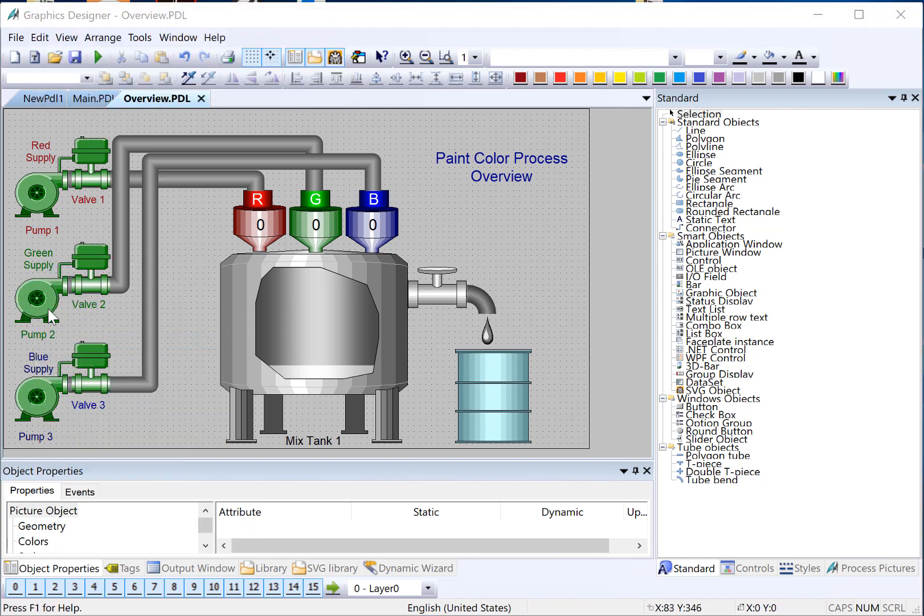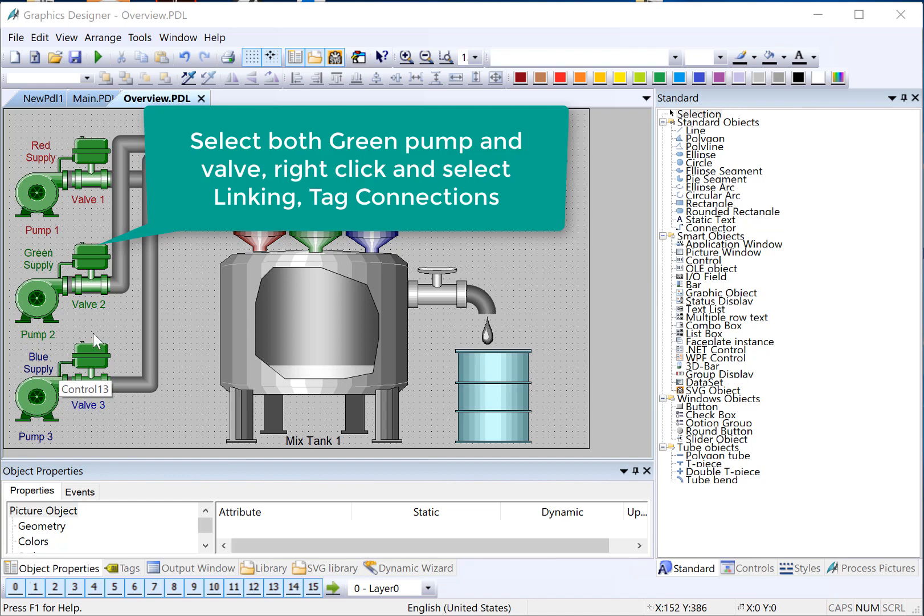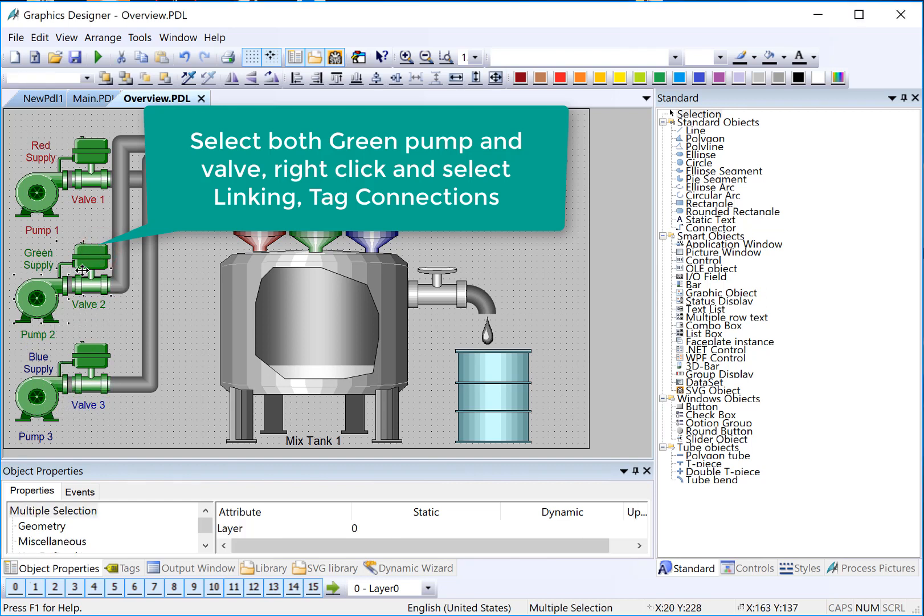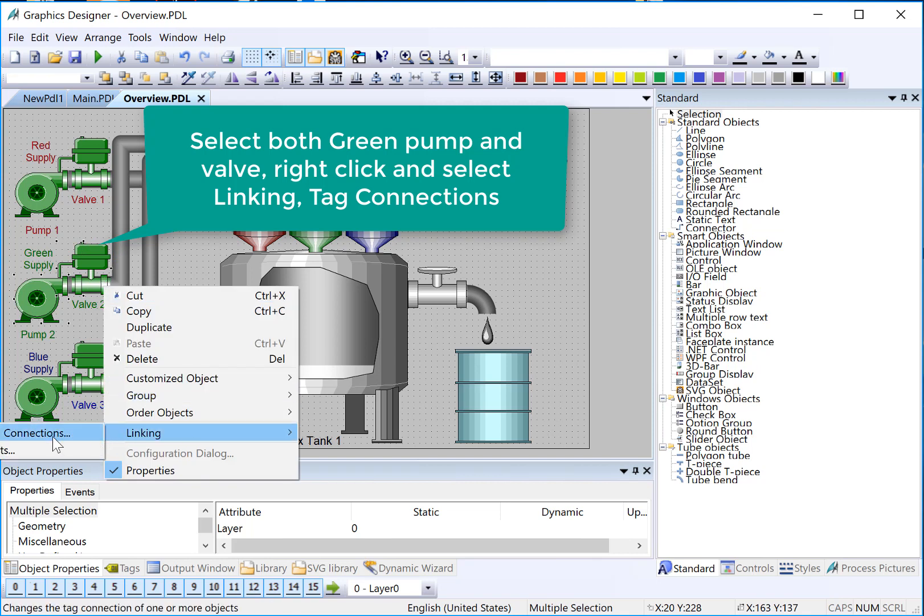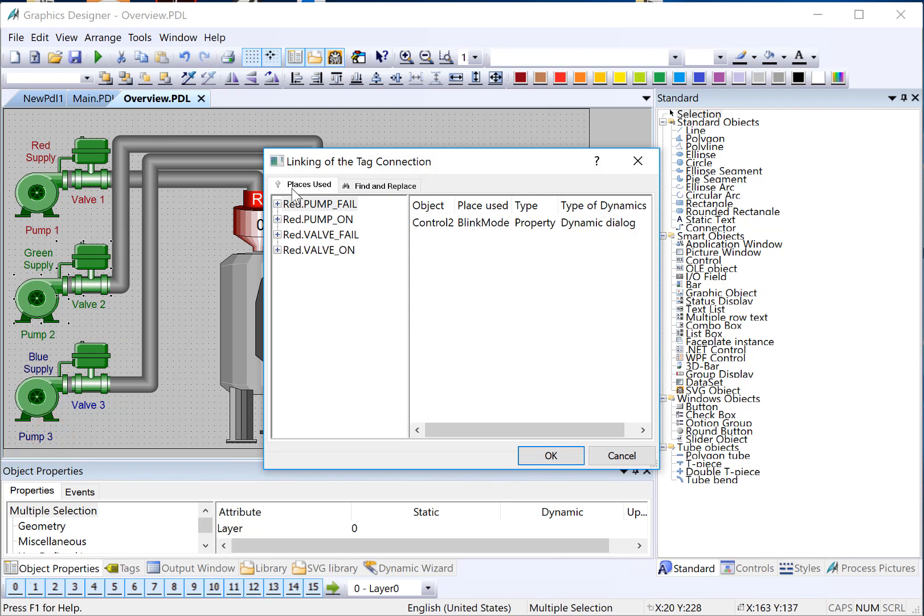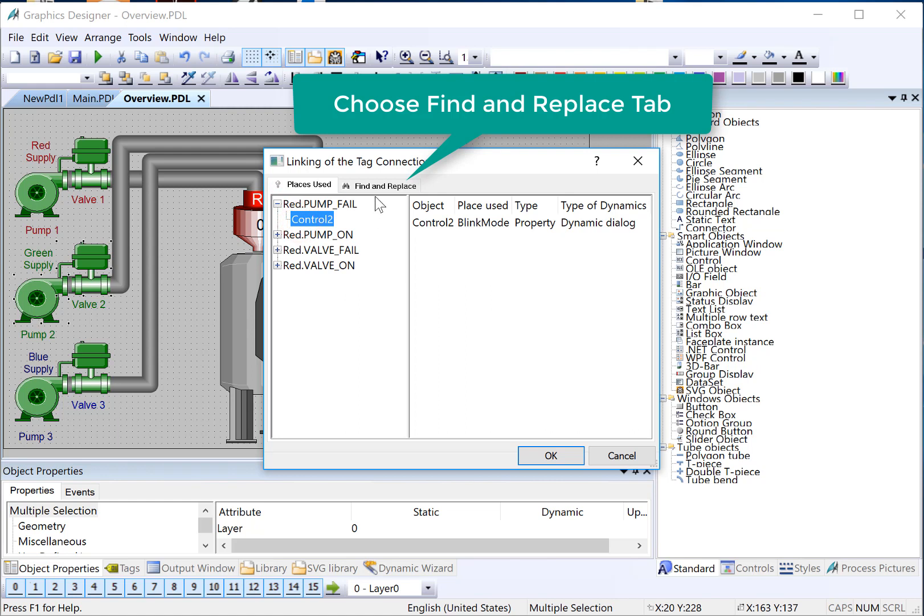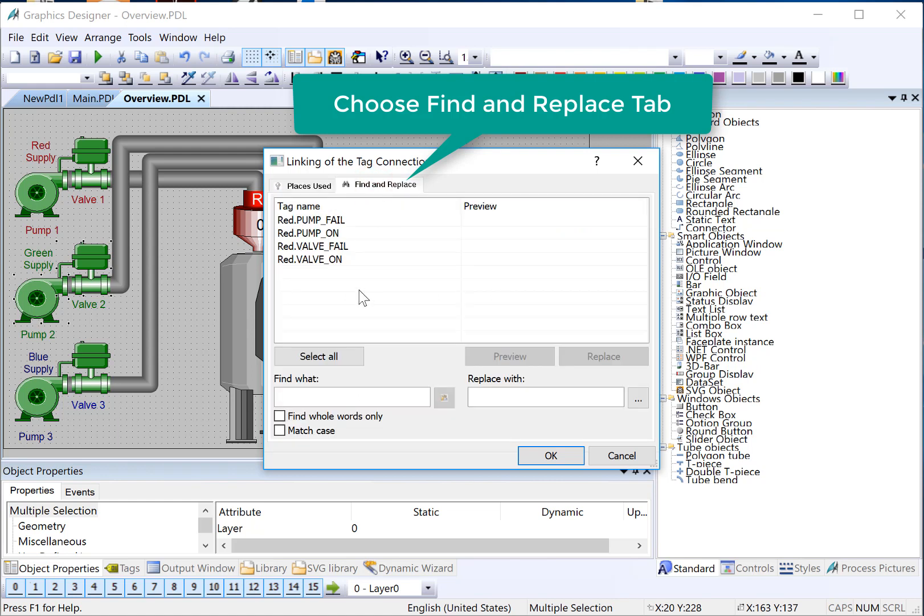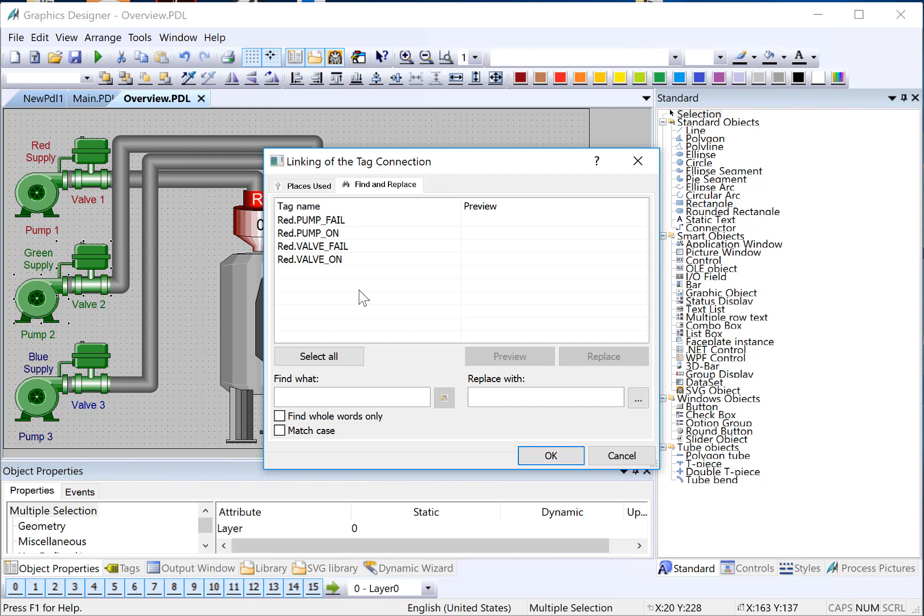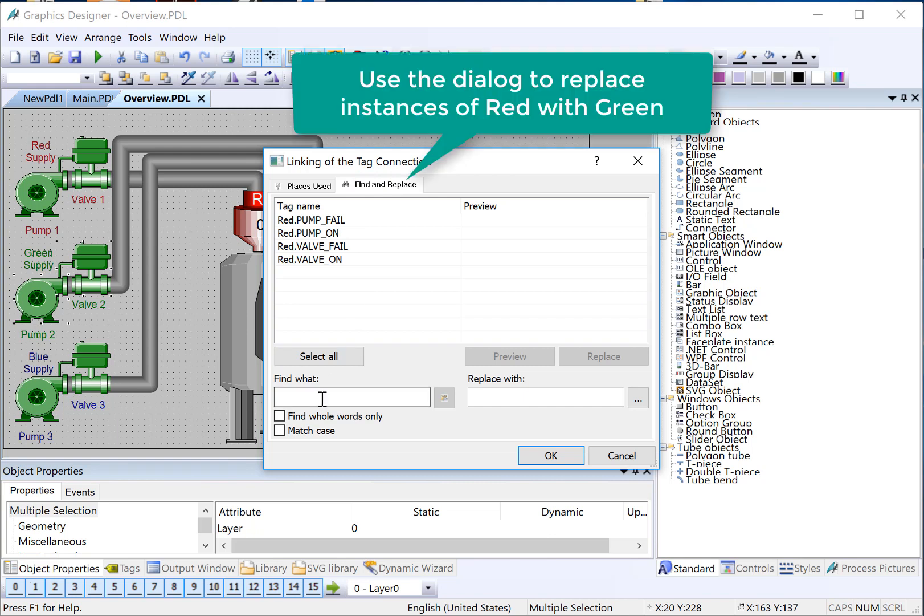Now that we have them duplicated, they still have the red tags associated with the dynamic dialogs, so we need to change that. I'm going to select my green pump and green valve, right-click, and choose linking tag connections. It's going to show me all the tags that are on these various objects. I'm going to go to the Find and Replace, and since we named our tags appropriately, red, green, and blue, I can just see that I need to change out red for green. So I just say, Find Red, Replace with Green.